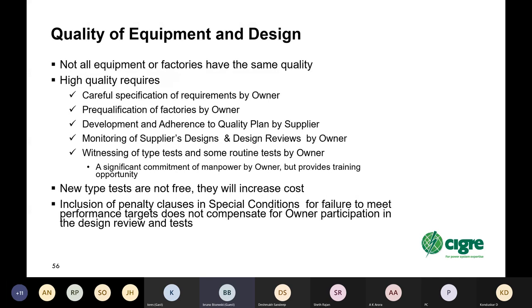I think it is a waste of money to specify type tests and then not go and witness them, because you could just as well, in that case, accept an existing type test. So when you're looking at what you need for quality control, if you specify new type tests, you should be witnessing them. The thing to remember is new type tests are not free. They will increase the cost, and if you don't witness them, all you get in the end is a certificate with a check mark which says passed, and you don't know anything of how your equipment performed during that test at all. So really not much value for the money.